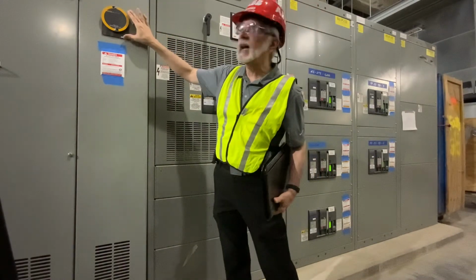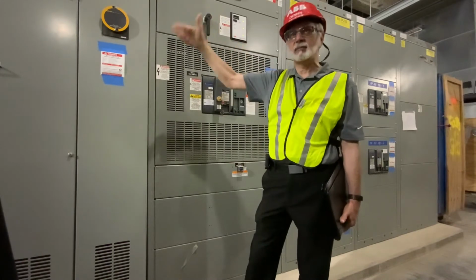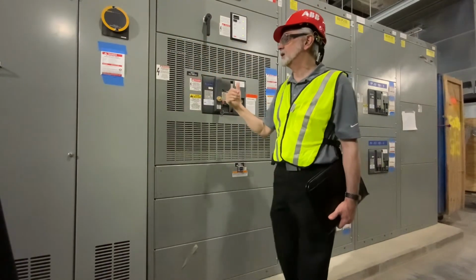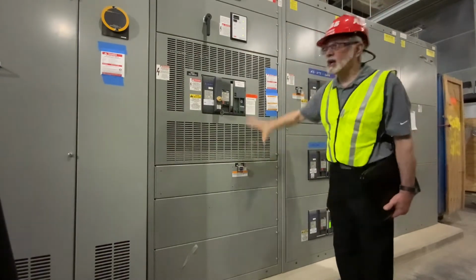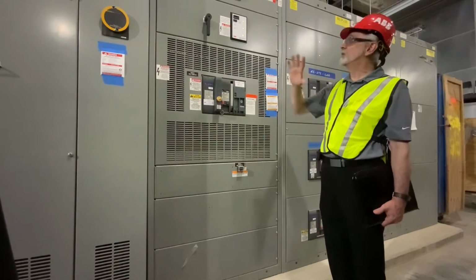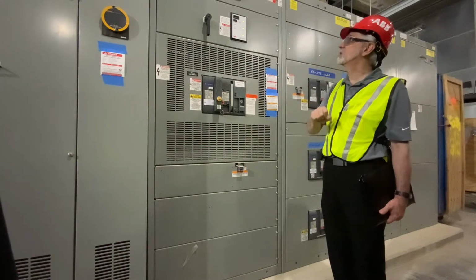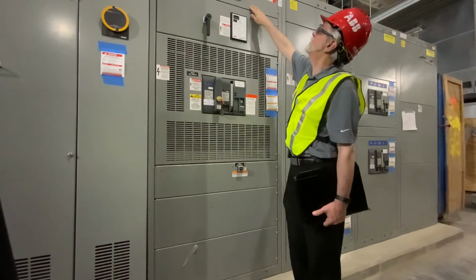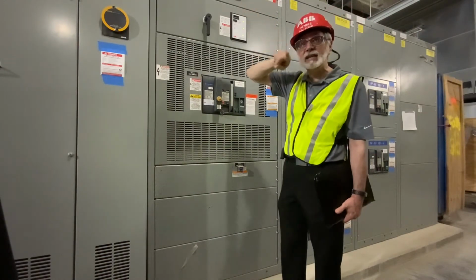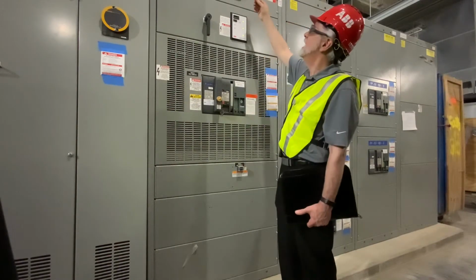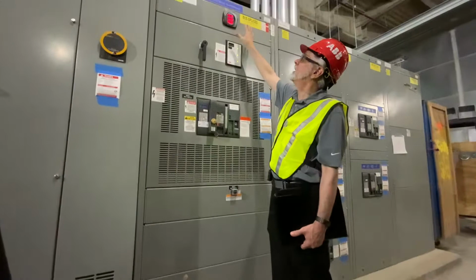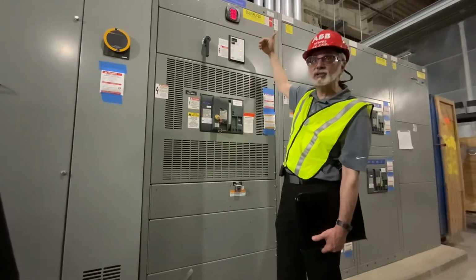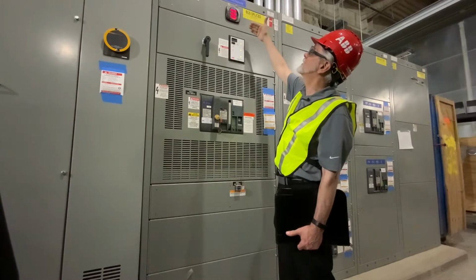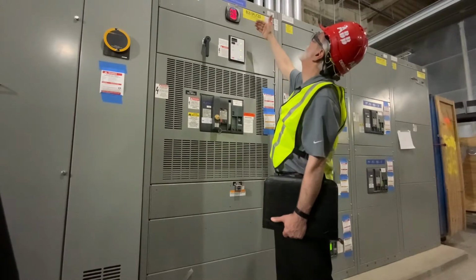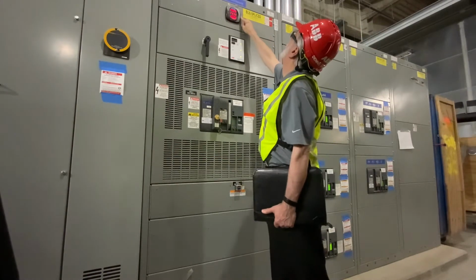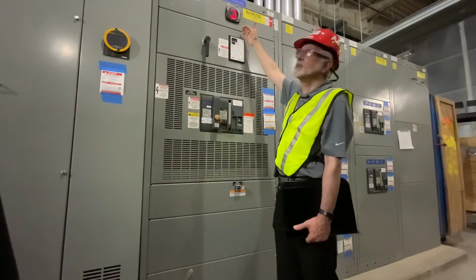You do have a sight glass in here, so you can take a look at the flex braid connections coming from the transformer onto the equipment. This is the main incoming section of your equipment. There are a couple of important components I want to talk about. The first one is your multifunction meter, which you have up here. As you can see, it's a little different looking than the one we saw on the medium voltage. This one is a little easier to read, and it automatically cycles through the various parameters. Now it's looking at the phase-to-phase voltages. Now it's looking at the amperage that it's pulling. This is pulling about 2,000 amps right now.